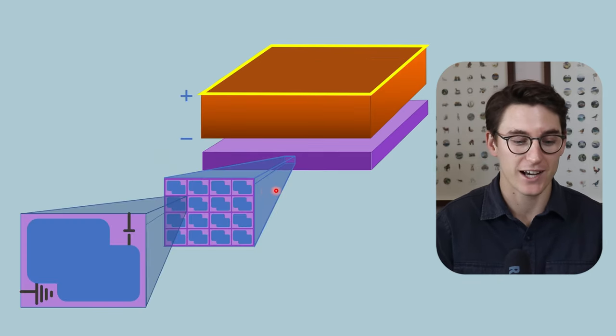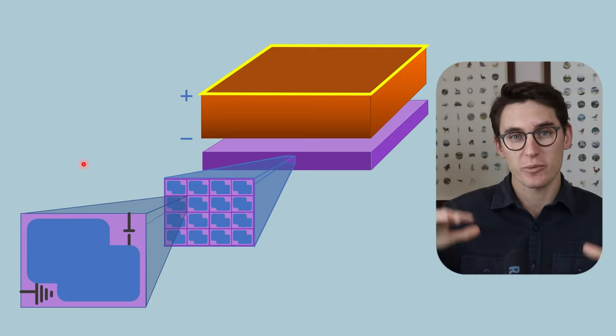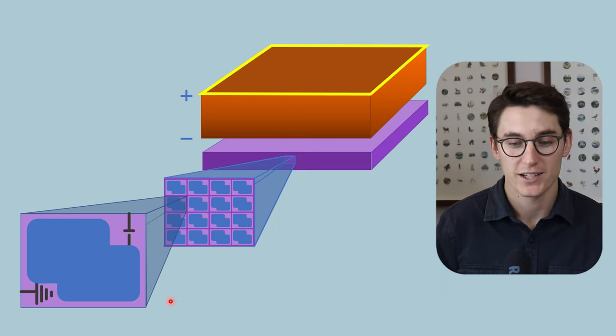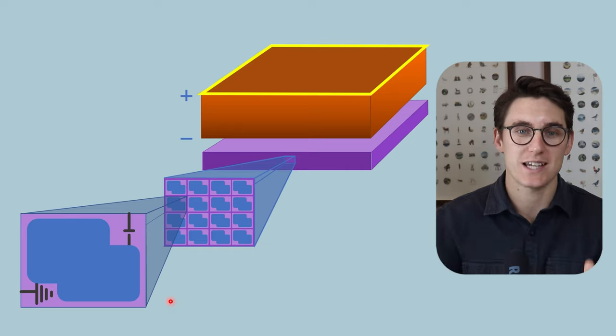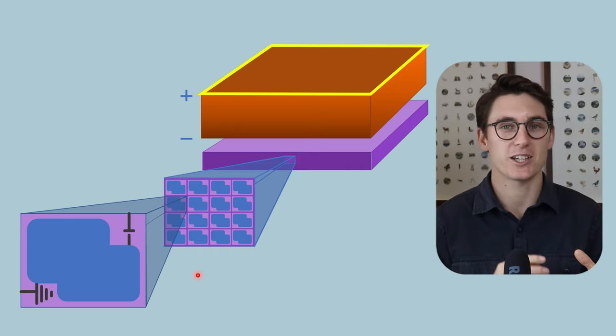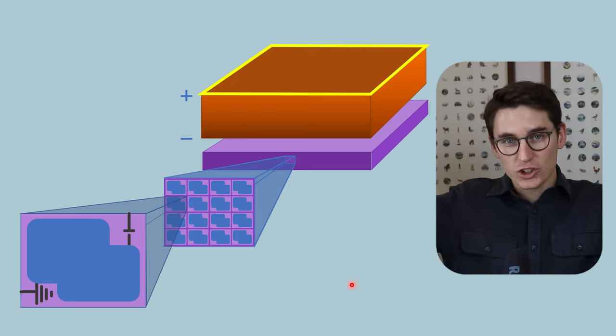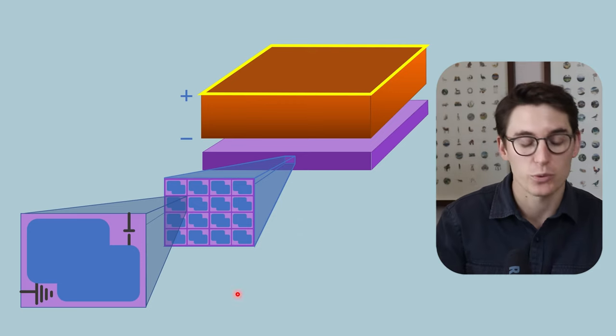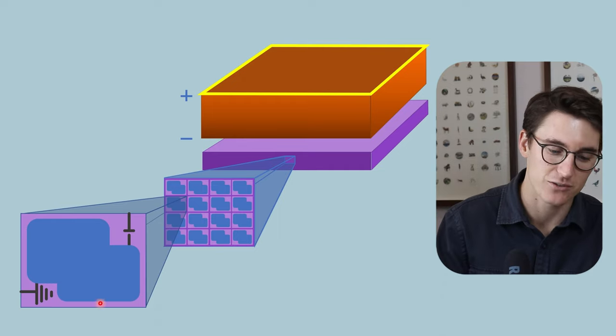The other thing here is when we looked at our dexels in our indirect thin film transistor array, we saw that photodiode indiscriminately let electrons down onto the entire dexel, and there were regions that were not sensitive that weren't contributing to the image. Now what we can do in our direct digital radiography systems is mold that electric current onto the sensitive area on our dexel. That fill factor is less of an issue here. We can ensure those electron holes are molded onto this sensitive area. We get great signal for the x-ray energy we are creating, without loss of signal onto non-sensitive areas.